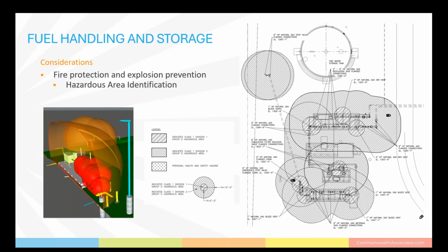Okay, final considerations in fuel handling and storage in regard to hazardous area classification. This is one of the reasons why the gas yard is typically located away from other equipment. Special care needs to be taken to identify the different designations between Class 1 Div 1 and Class 1 Div 2 hazardous areas. There are 3 important reasons for the identification and modeling of these areas in the layout of the electrical system: to make sure that any electrical equipment within those hazardous areas is rated accordingly. They're identified to make sure that no air intakes to HVAC equipment or into the building are within the identified areas. And finally, when working through the NFPA Life Safety Plan, to make sure that emergency exit paths do not pass through those areas, or that the clear path to safety does not extend into any of those same areas.